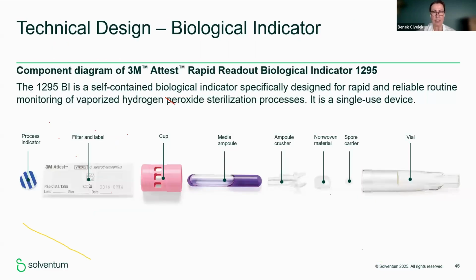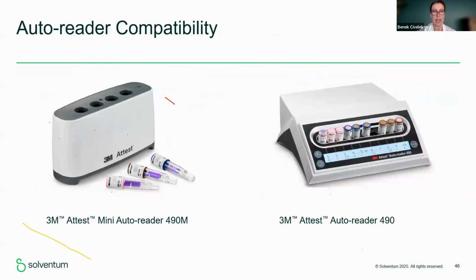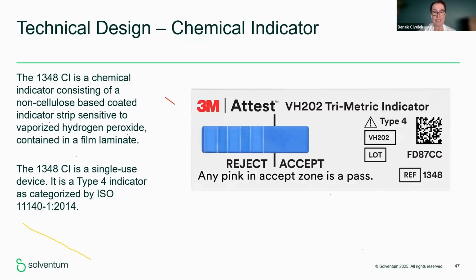We talked about the technology of steam in the previous slides. Here, the same technology applies for 1295, also the same design and same certification. And we talk about the same safety features for the autoreaders. And I told you that the prevention of errors from the human also should be an important factor to choose the right autoreader. We have talked about the technical design of a type 4 indicator. Again, this should be certified as a real type 4 according to ISO 11140-1.